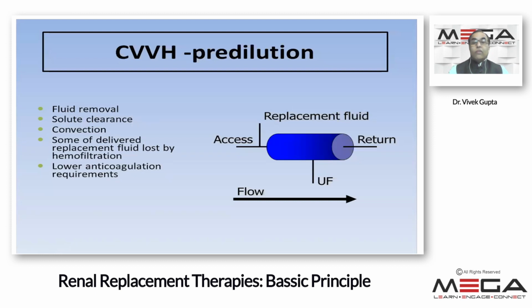So what are the benefits of the pre-dilution? When we do a pre-dilution, the blood is getting diluted, so solute clearance will be compromised, but the filter life will definitely increase because you are diluting the blood.